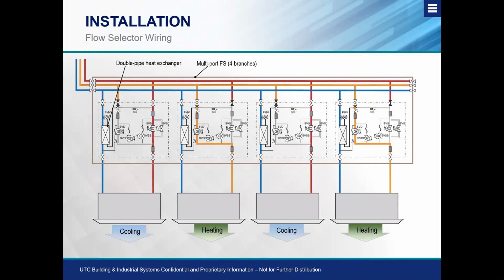So moving over to the multi-port box, these are available in 2 configurations. As you can see here on this slide, we have a 4-port configuration and a 6-port configuration. So with the 4-port configuration, you can see we have 4 ports and generally we have 2 more things. Solenoid valves, double pipe heat exchanger helps subcool that liquid refrigerant. And we have multiple units that experience different thermal loads connected to one flow selector branch box, however you want to refer to it.